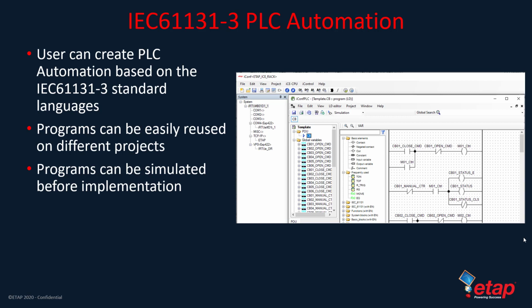This device is also, as we were saying, an automation controller. It's capable of supporting all of the IEC 61131-3 PLC automation standards. So this device can be used to create programs that can be used in the substation to perform different applications, such as protective device control, motor control, transformers, or even controlling an entire substation. You can create multiple programs and reuse them across projects on your ETAP Ice device.